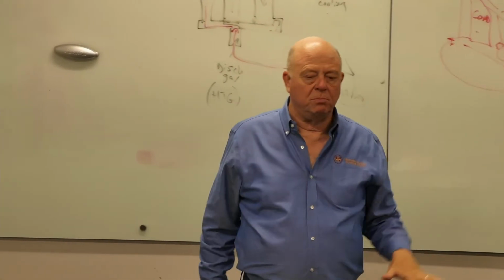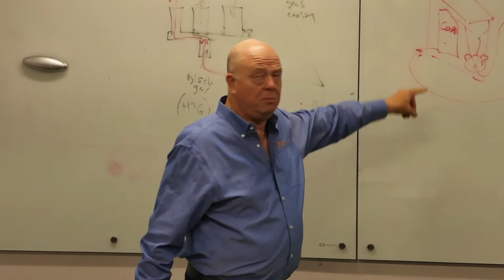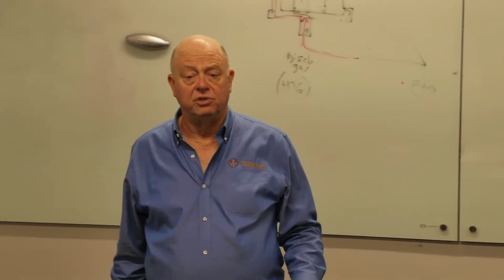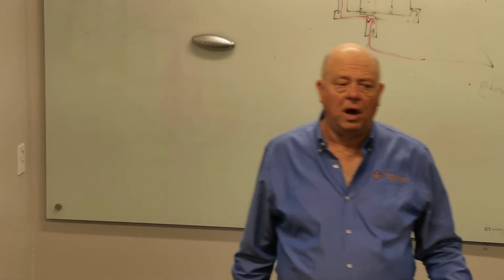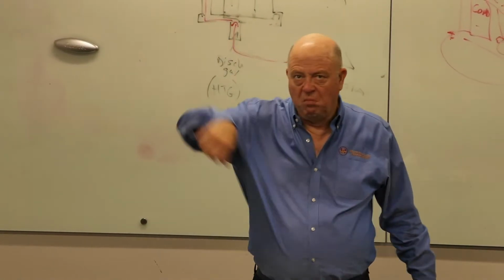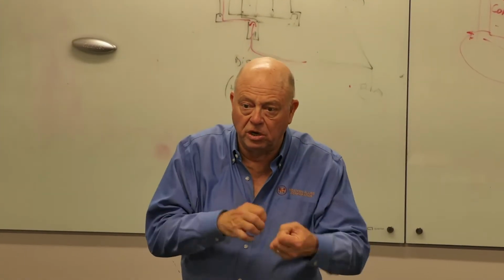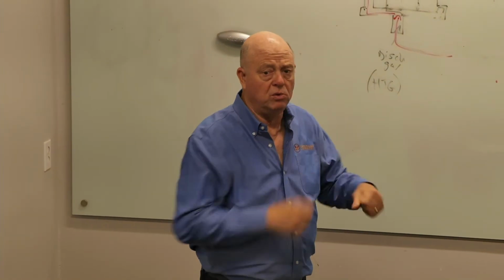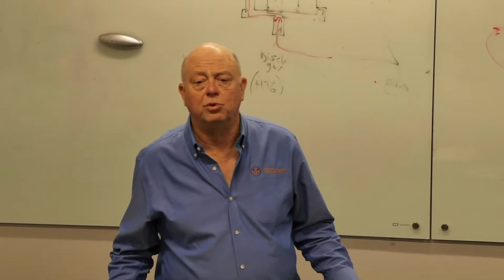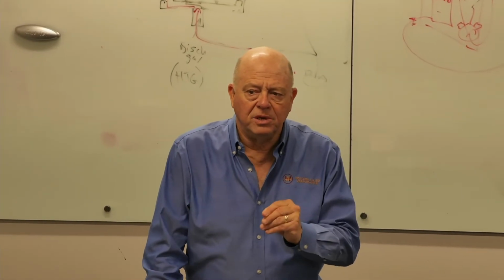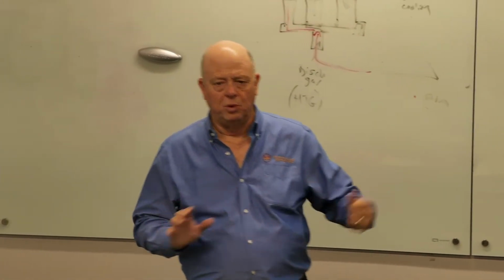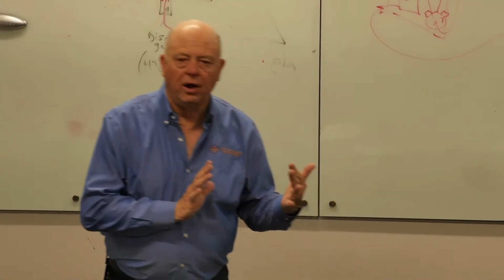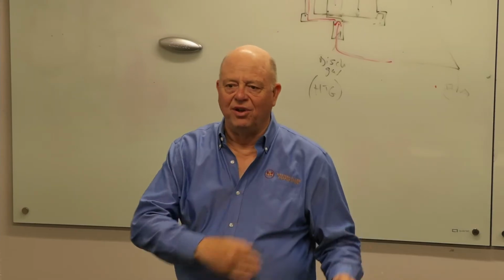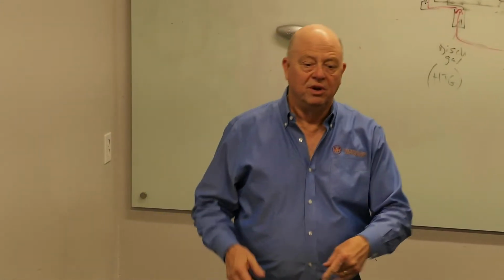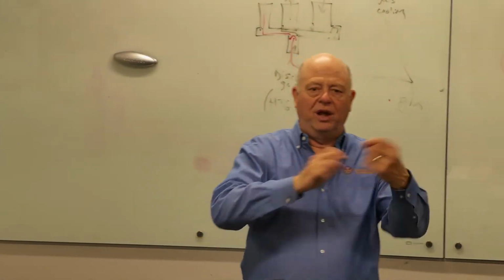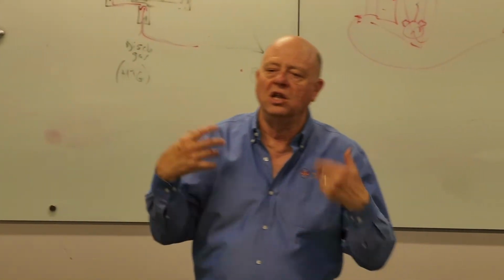Look, connection, connection, connection. We, as a service department, typically, if we've had a compressor failure in a heat pump, we also replace the reversing valve. Does it always need it? No. I'm going to say it needs it 35 or 40% of the time, because it gets so gunked up from the stuff that came from the compressor failure that it won't move smoothly anymore, or pretty soon it won't. Problem is, if you don't replace the reversing valve at the same time you replace the compressor, and it dies, you're back there having just done the compressor. You have to take it offline, you have to pull all the refrigerant out again, you have to do all the new filter dryer, all of that kind of stuff.